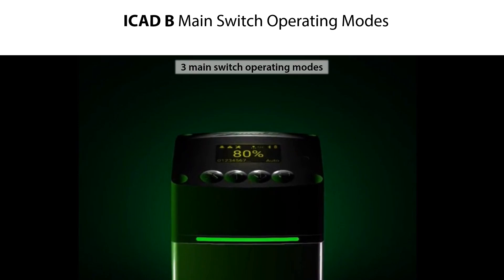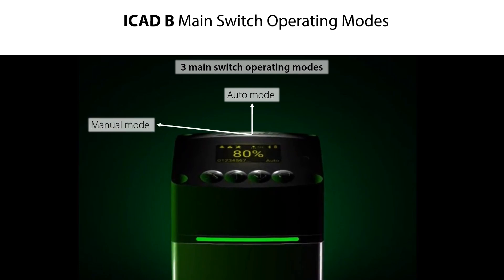There are three main switch operating modes: Auto mode, where the valve position is controlled by an analog input signal; Manual mode, where the user manually sets the valve position to be maintained; and Config mode, where the ICAD-B continues a given operation but where parameters can be changed and applied to the ICAD-B.